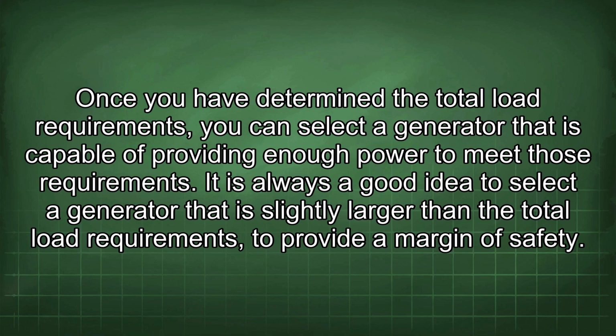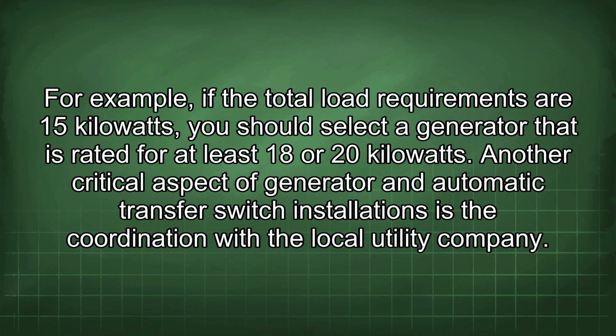Once you have determined the total load requirements, you can select a generator that is capable of providing enough power to meet those requirements. It is always a good idea to select a generator that is slightly larger than the total load requirements to provide a margin of safety. For example, if the total load requirements are 15 kilowatts, you should select a generator that is rated for at least 18 or 20 kilowatts.